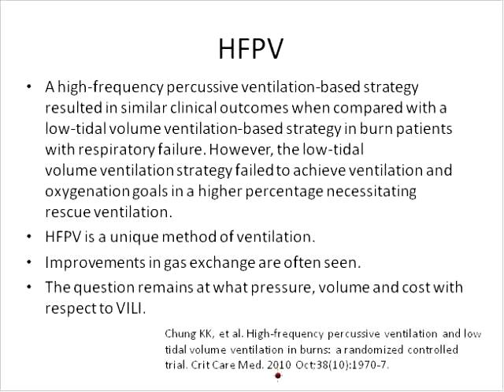I never doubt Dr. Bird at this point. High-frequency percussive ventilation is definitely a new method of ventilation. We often see improvements in gas exchange. The problem that we continue to have is the monitoring with the VDR is not as sophisticated as you get with the ventilators that we're using consistently, and simply looking at the manometer on the top of the machine is not sufficient. And we need to know when we have patients on the VDR and they have better gas exchange, at what pressure cost, at what volume cost is that with respect to ventilator-induced lung injury.